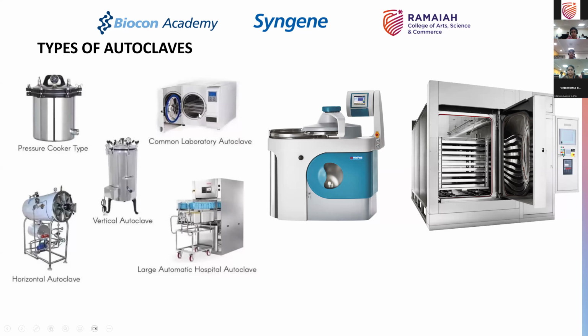Again, this can be clubbed with a vacuum pump for proper drying, but generally for a pressure cooker type and a laboratory autoclave type, the material will probably come out much wetter as compared to the large autoclaves which you use. But this can, of course, be clubbed with a vacuum pump to dry the loads. So no issues about it. We can achieve the drying.